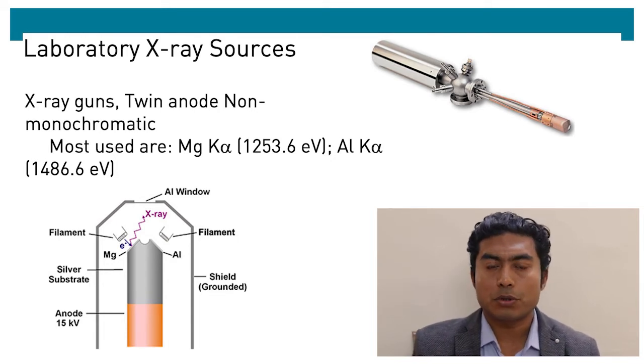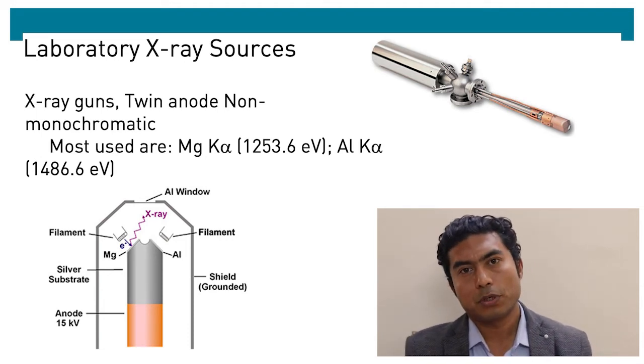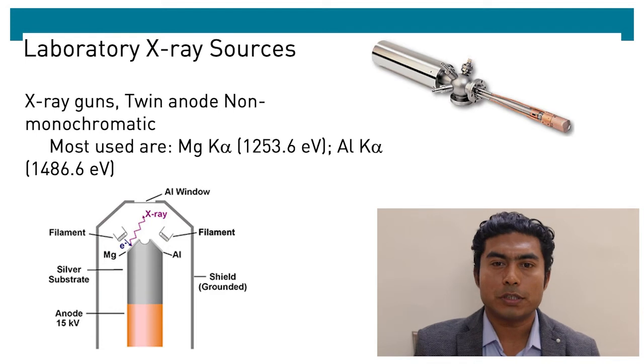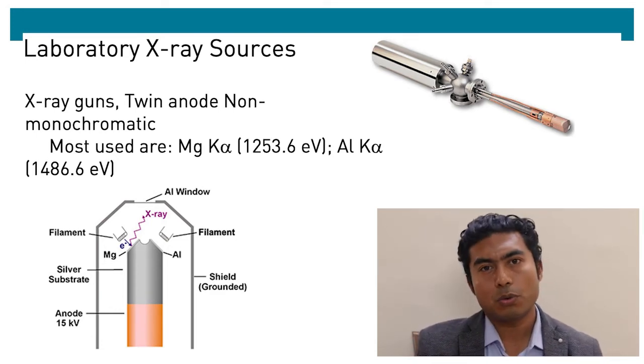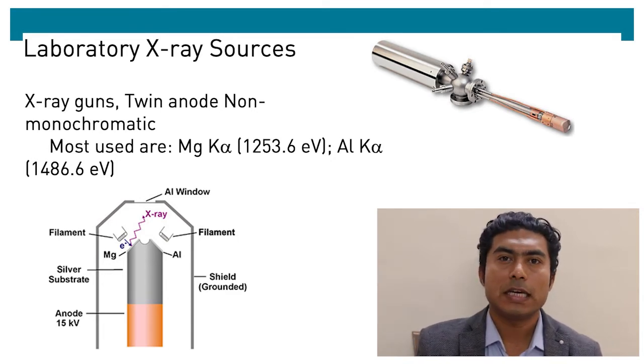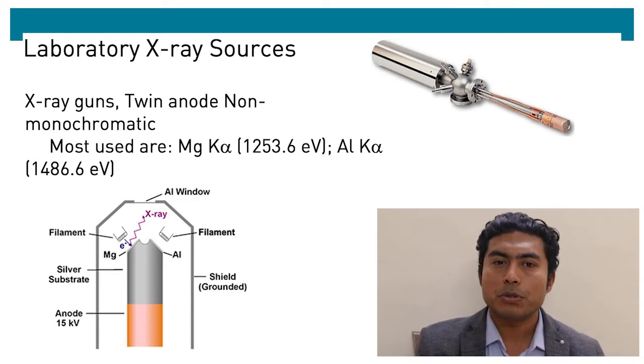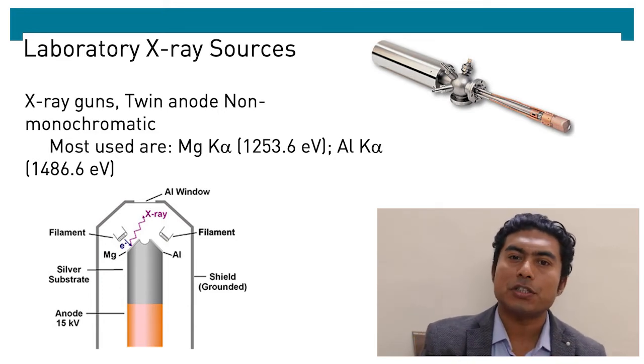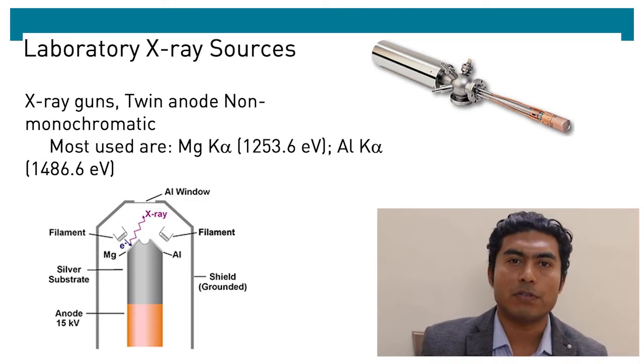Two types of X-ray sources we will discuss here. One is the twin anode or dual anode sources. In twin anode sources, we have two metal anodes, magnesium and aluminum, and they can be used one at a time. The basic operation principle is that from a filament, electrons are produced and they target the metallic anode which causes excitation in the core levels. During the radiative decay of excited electrons, they emit characteristic X-ray of the anode.